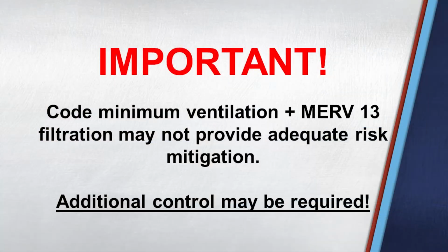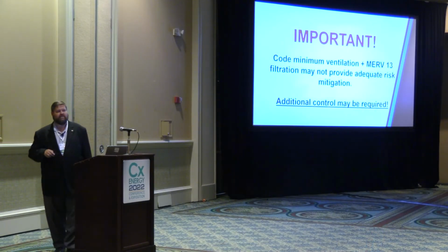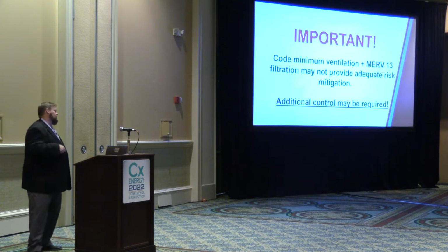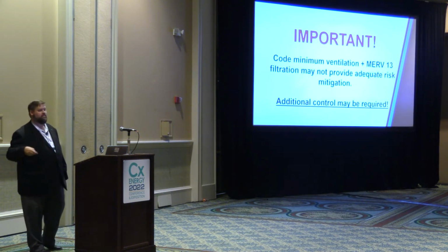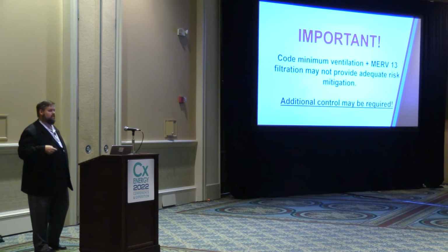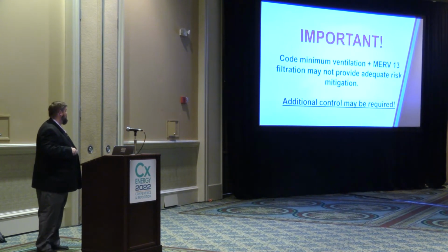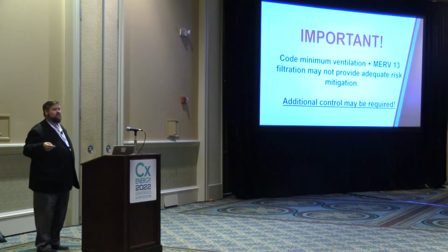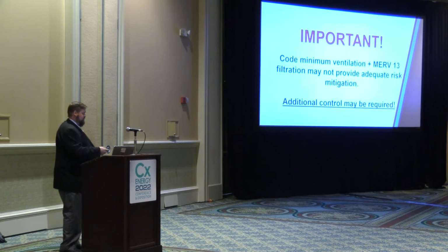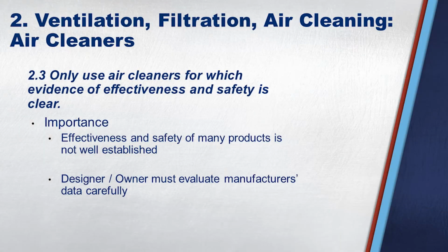Imagine Dr. Bill Bonfleth standing on a soapbox because he keeps reminding people that code minimum outside air, MERV 13 filtration, may not be enough for the risk mitigation in your space. So if everyone in the room is exercising, playing musical instruments, or doing something with a higher likelihood of close contact like wrestling, that may not be enough. You might need more than just that. Use air cleaners for which evidence of effectiveness is clear. I really just want to skim over that.